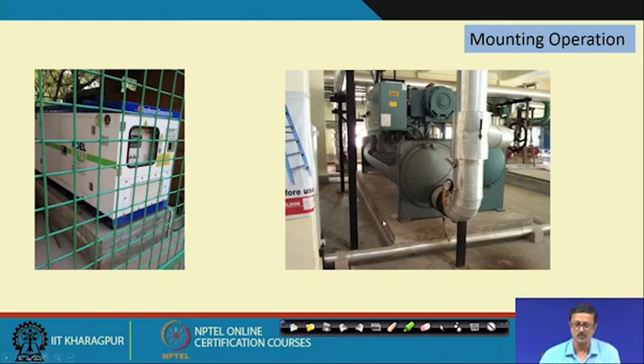This other machine is the central air conditioning system, placed in a classroom complex near our IIT Kharagpur campus. Here the inertia block has two splits, you can see a black line marking this split. The inertia block is split into top and bottom parts, and the central sandwich area is filled with a felt or cork sheet layer. So this is another arrangement where the mounting or inertia arrangement is handled with special criteria.